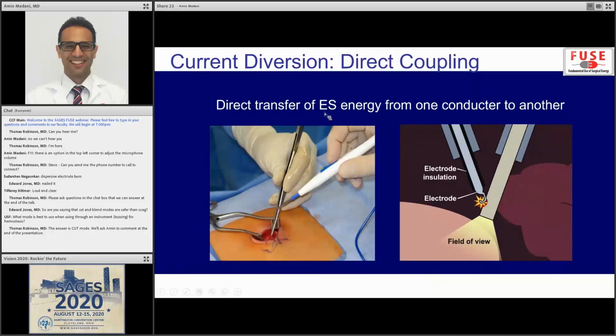The other type of problem is called direct coupling — directly coupling your conductor, your active electrode, to another conductor. When you say 'buzz me,' you're doing direct coupling intentionally in that case. But if your metal is touching another metal inadvertently, you can divert current and cause a burn like in the skin here. Or in laparoscopy, you could touch the laparoscope, activate it, and then it touches bowel, let's say. So direct coupling is another thing to be careful of — always make sure your tip is in your field of view and never activate it inadvertently.